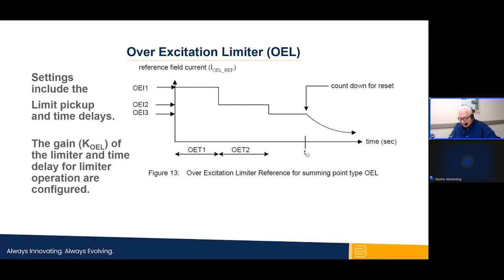The limiter includes a tolerance for short duration overexcitation within well-established characteristics for the machine's capabilities. IEEE standard 421.5 provides guidance for setting these limiters. The field winding shall be capable of operating at 125% of rated load field current for at least 60 seconds. Starting from stabilized temperature at rated conditions, higher currents are permissible for shorter durations. For example, 209% rated load field current for 10 seconds. The relationship between the level of overexcitation and the time limit is normally characterized as inverse time functionality.